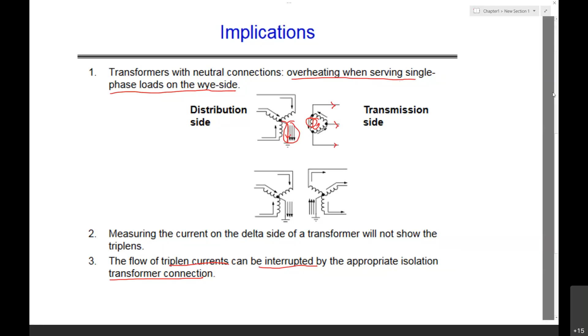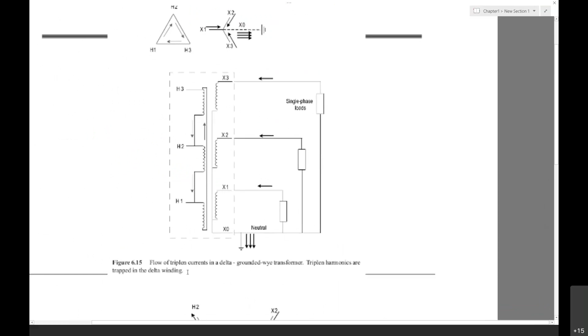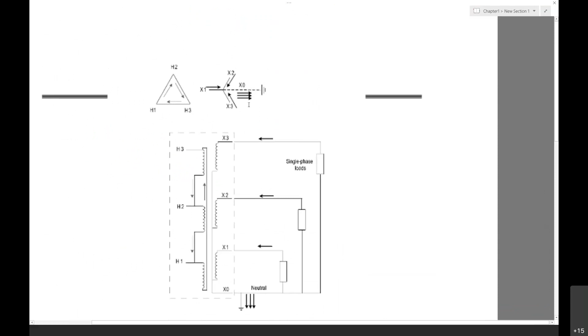Basically, if you have a transformer which doesn't have the neutral winding, if you isolate the primary side and the secondary side, then we'll not have the triplen harmonics. Next, this is one case of the transformer: the flow of triplen currents in a delta grounded-wye transformer is trapped in the delta winding, whereas the triplen harmonics will be there on the star side. You already know this.